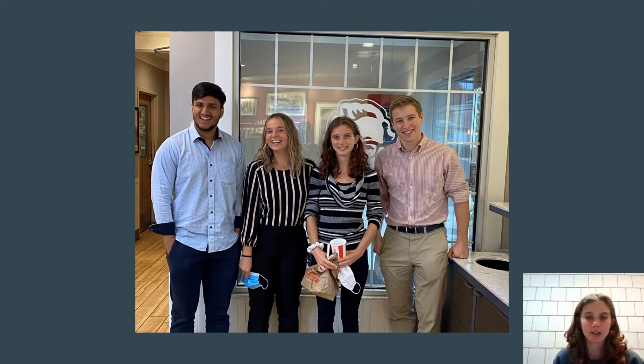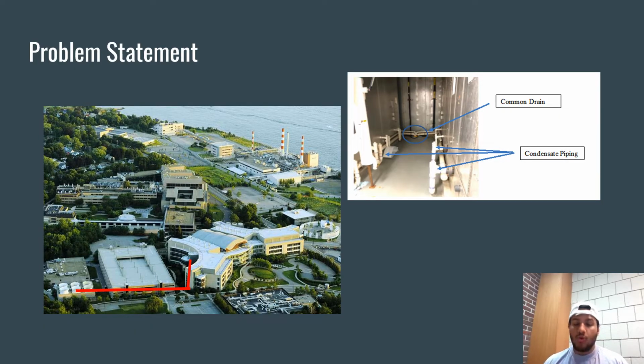Our team is a combination of the environmental and mechanical engineering departments at UConn. The Pfizer facility in Groton uses 225 million gallons of water per year, which puts it as the top consumer globally in the portfolio of Pfizer facilities. Right now, there are 22 air handling units that are collecting the condensate and draining it in the sewer, as you can see in the picture on the right. Our job is to design a system to collect the condensate and treat it and send it to the cooling towers, as you can see in the picture on the left.